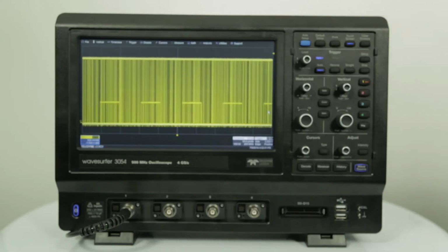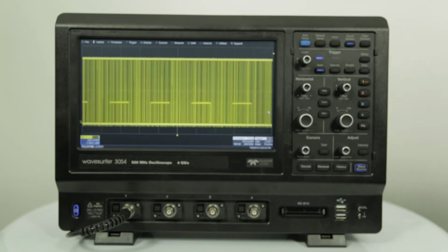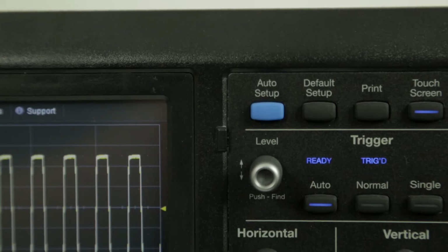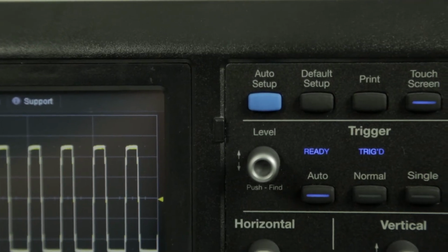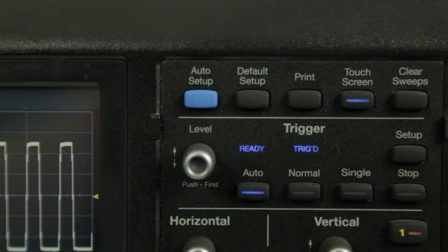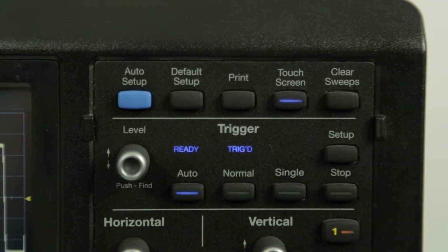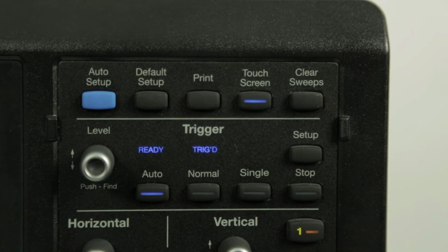The next step is to set up the appropriate trigger that will allow you to capture the waveform. The trigger controls allow you to stabilize repeating waveforms on the display or to capture single-shot waveforms. The front panel control contains six different controls for setting up the trigger: the level knob, auto button, normal button, single button, stop button, and setup button.